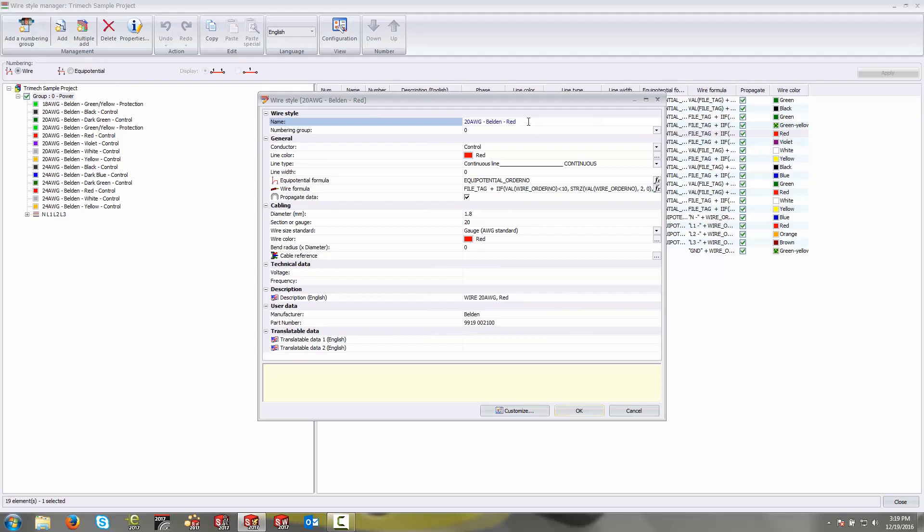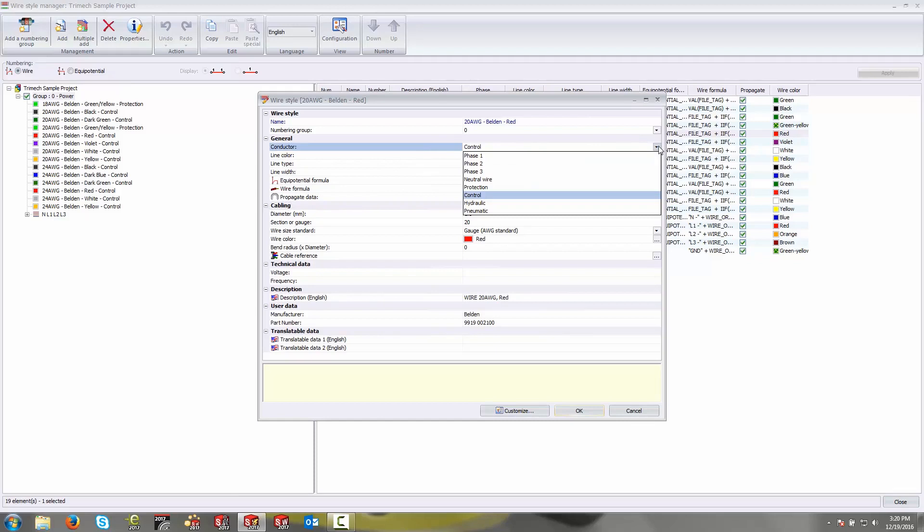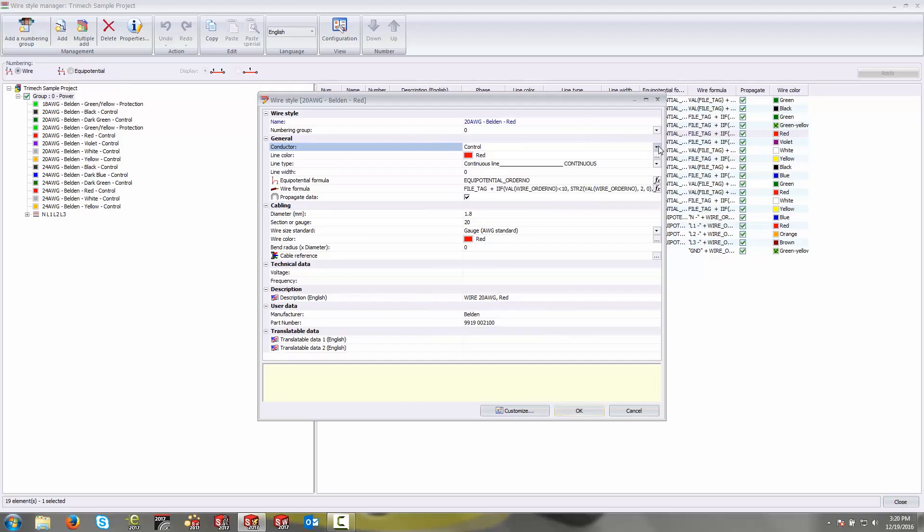At the bare minimum I usually like to have gauge and color. Down below you have information related to how this wire is going to be represented on a schematic drawing under general, and under cabling you have information related to the physical wire itself. The conductor grouping is really just a way of grouping these wires together according to some kind of parameter like phase one, phase two, neutral wire, protection, control. Most wires that aren't going to be used for power or may just be miscellaneous in nature, you can keep under control or phase one.